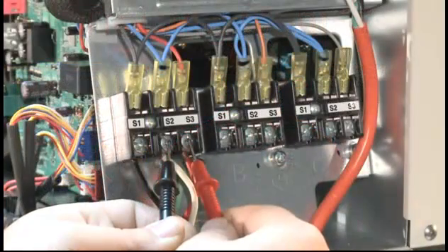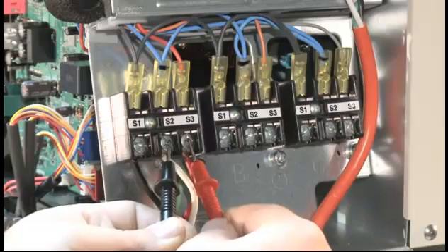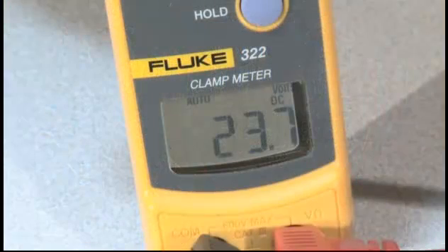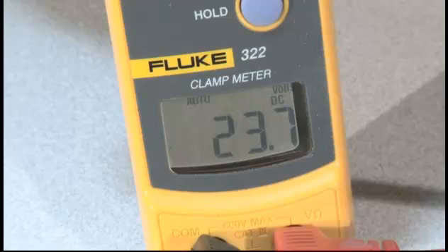Having a steady 24 volts DC at the S2 and S3 with the wires connected will be a cause of a communication error. Checking this can be done by measuring your DC voltage across S2 and S3 of the outdoor unit. If while checking you notice you have a steady 23 to 27 volts DC, there is a good chance we have a break somewhere in the wire or the indoor board is bad.